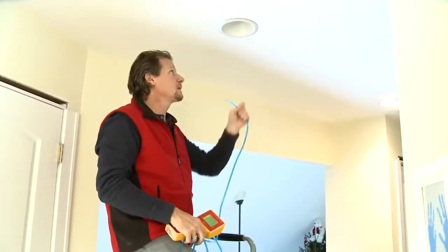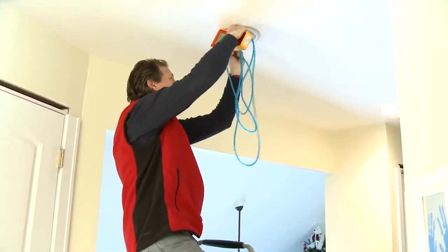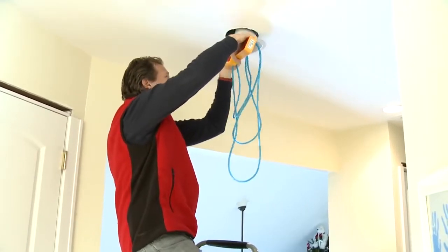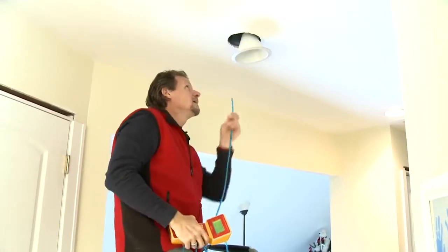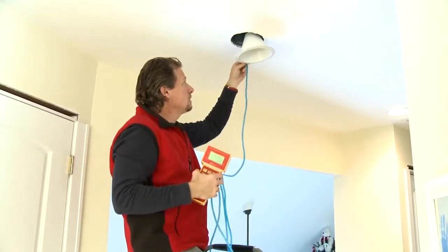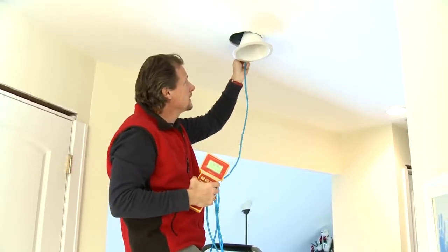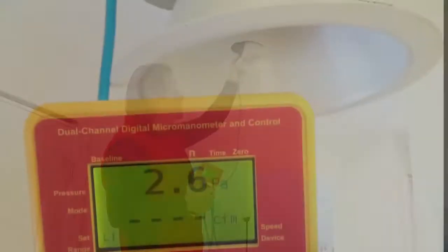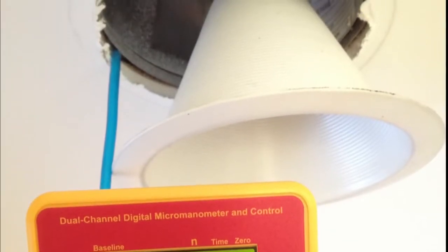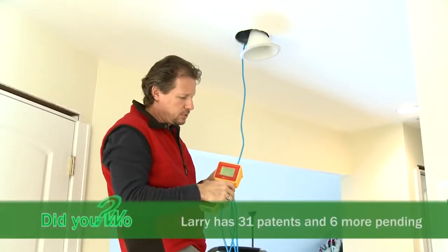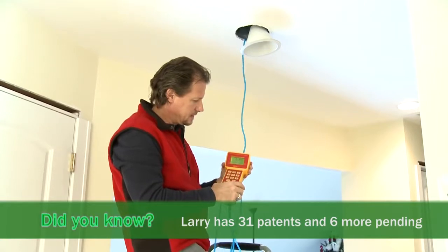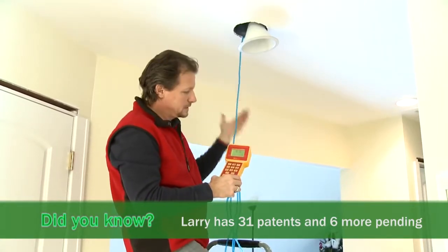Now we talk a lot about can lights and how they leak. Let's take a look. And this particular can light, it has holes in the housing. There's also a hole around the drywall to the housing, and I can stick this hose right up into the attic. And we can check the pressure difference across that can light. We know that there's holes because we can see them.